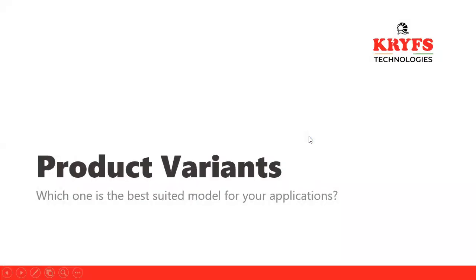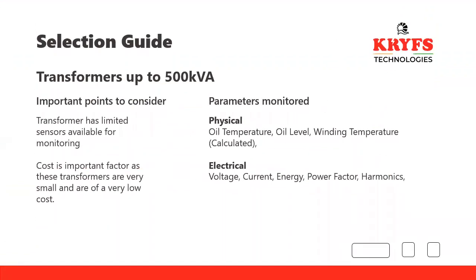So this was about the technology which we are using. So now coming to the product variant, different product varieties what we offer. So we have segregated the product based on transformer size. For transformers up to 500 kVA, the important point to consider is the transformer has very limited number of sensors installed. Actually, there are no such sensors. All physical visual indications are present, but sensor transmitters are not available.